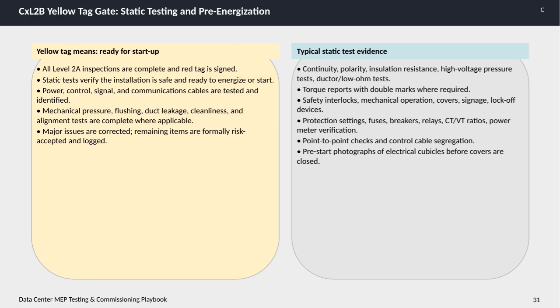Typical evidence of static tests includes continuity, polarity, insulation resistance, and high-voltage pressure tests, as well as low-ohm tests. Additional documentation includes torque reports, especially where double markings are required, and verification of safety interlocks, mechanical operations, covers, signage, and lock-off devices.